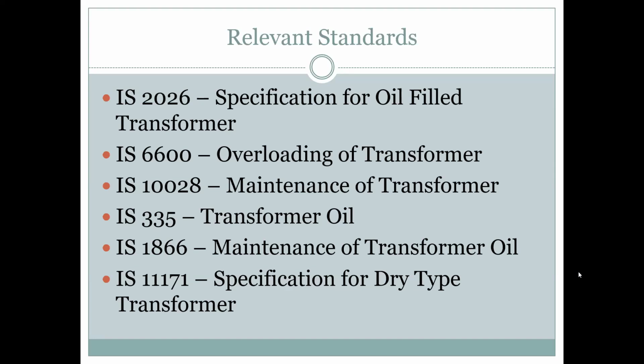Now, many people ask, if I overload the transformer, then what will happen? Suppose one transformer fails, the other transformers have to take the additional load. This is very, very dangerous and has to be looked into very minutely. There is a guiding standard for overloading of transformers, that is IS 6600. A transformer is supposed to deliver all its guaranteed parameters under specified conditions and specified testing. Overloading is not allowed, but sometimes we are bound to overload transformers. This overload factor is guided here with the details. We have to find out how much overloading we are going to give.